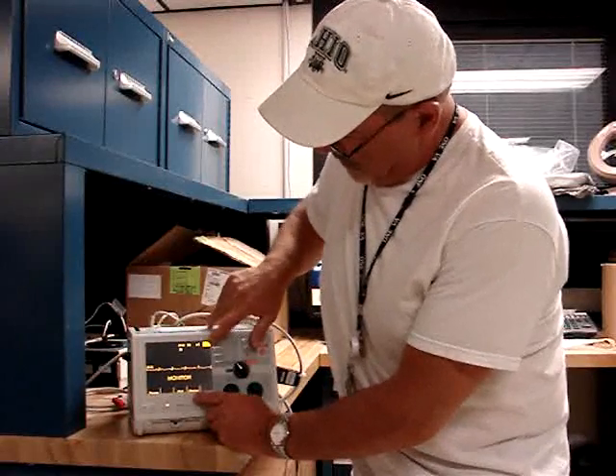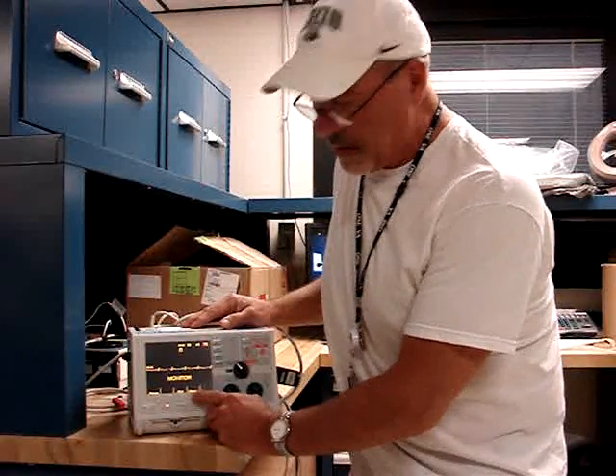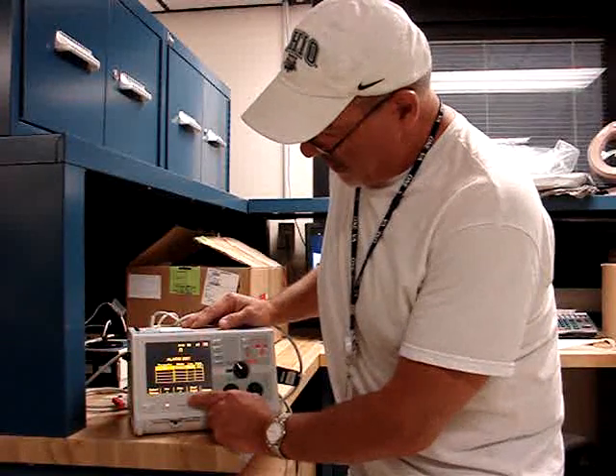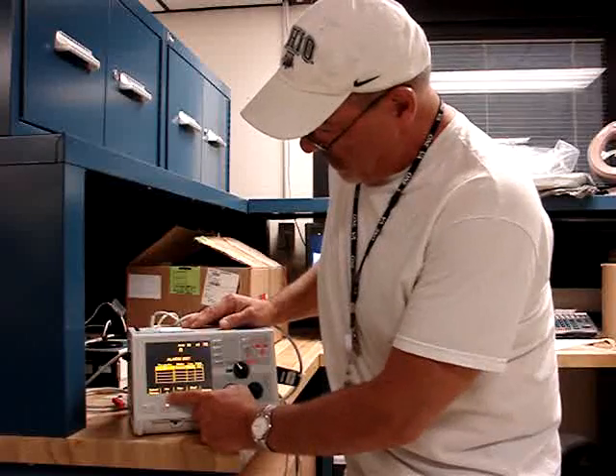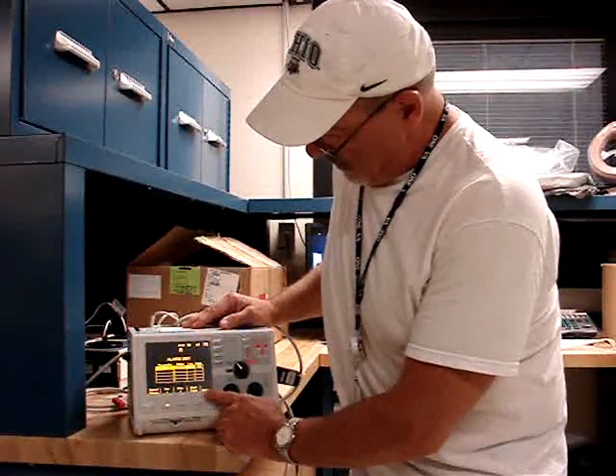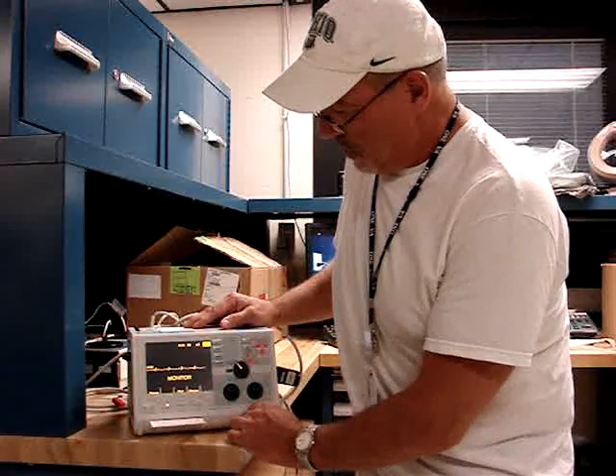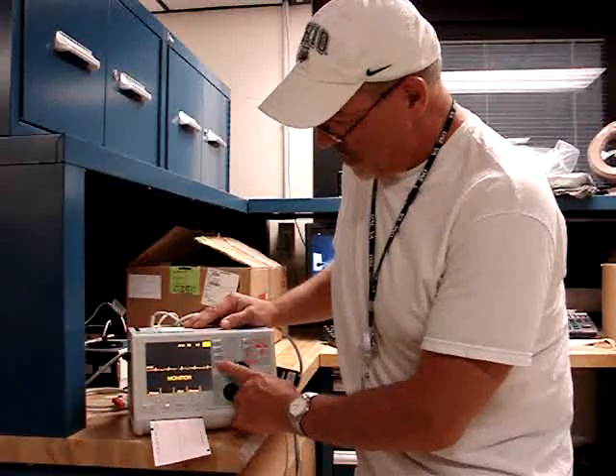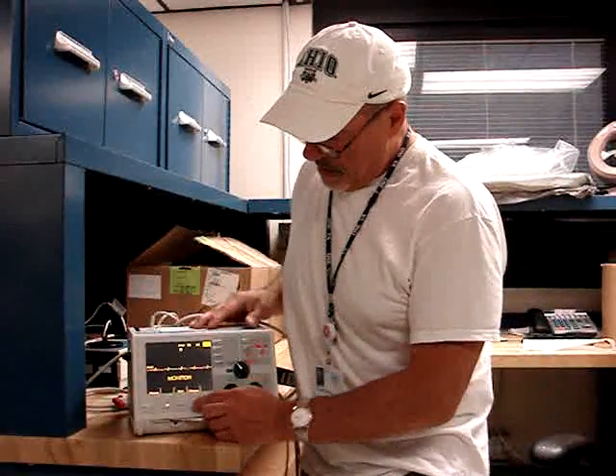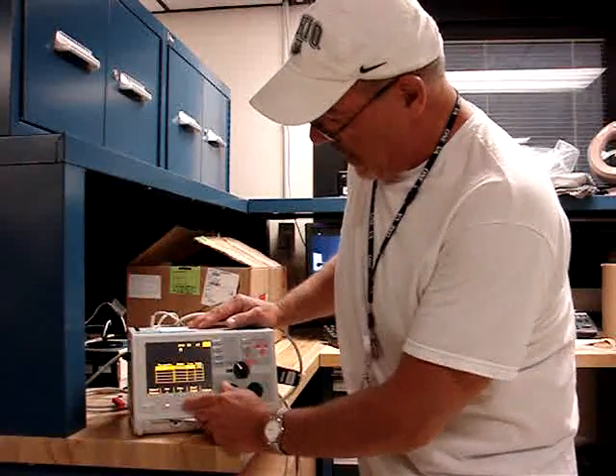Okay, on the alarm section of the defibrillator, it's set at a heartbeat of 72. So we're going to have to set the low end up above 72 to get the alarm to go off. So we're set on 70 right now. So we're going to take it up to at least 75. Make it 75 and return, and we should get a warning and it's going to record, which it did. Working fine. Suspend the alarm. The next step is we're going to reset that back down to 30.